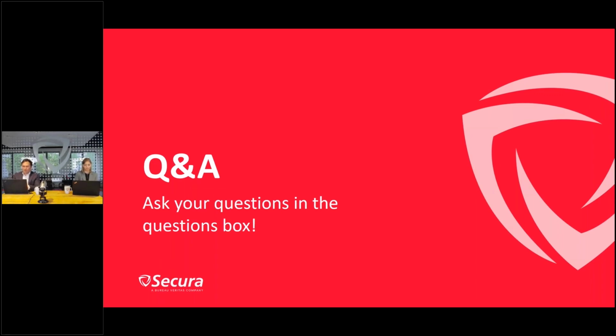That's a very good question. In general, regarding classification of devices, there are some gray areas. An MRI device is a pretty complex system, and at the same time, it's also a higher risk system. If an attacker is able to hack into an MRI device, that will have a very important security impact on the functionality of the device and also on the data the system is processing. So from that point of view, my suggestion for classification would be, in terms of the European Medical Device Regulation, to go for at least class 2, but potentially, if the risks of usage are quite high, to go for class 3.